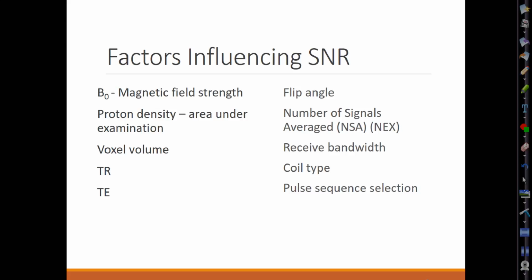So say when they order a scan like that, does the ordering physician know that, for example, they're going to send them to a place where they have the right magnet? Yeah, I mean, so for breast imaging, the ACR guidelines say they have to be at a 1.5 Tesla or above. Oh, okay. So if you do have a 3 Tesla, that's a luxury, but you do have to scan certain areas of the body under certain magnetic field strengths. So you have prostate and breast imaging, usually 1.5 and above.